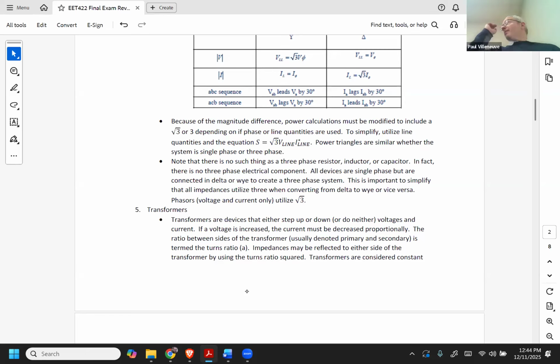I'm harping on that because it's a very common misconception. People just assume that's a three-phase device. It's not. Same thing with a motor. Your motor that you connect is a three-phase motor, but if you pulled the wiring out of the motor junction box, you'd actually find 3 independent leads that go into the motor. Again, you connect it in delta or Y to make the system.